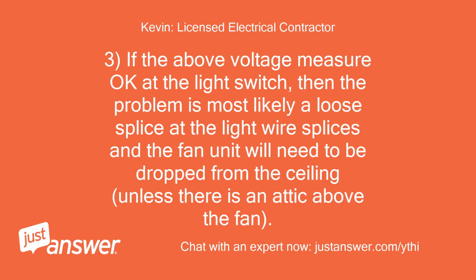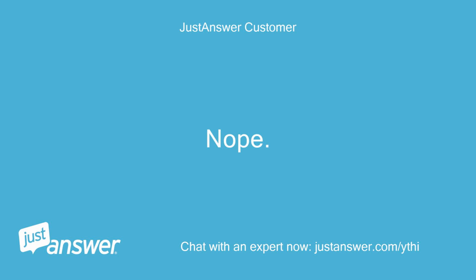3. If the above voltages measure OK at the light switch, then the problem is most likely a loose splice at the light wire splices and the fan unit will need to be dropped from the ceiling, unless there is an attic above the fan. Nope.